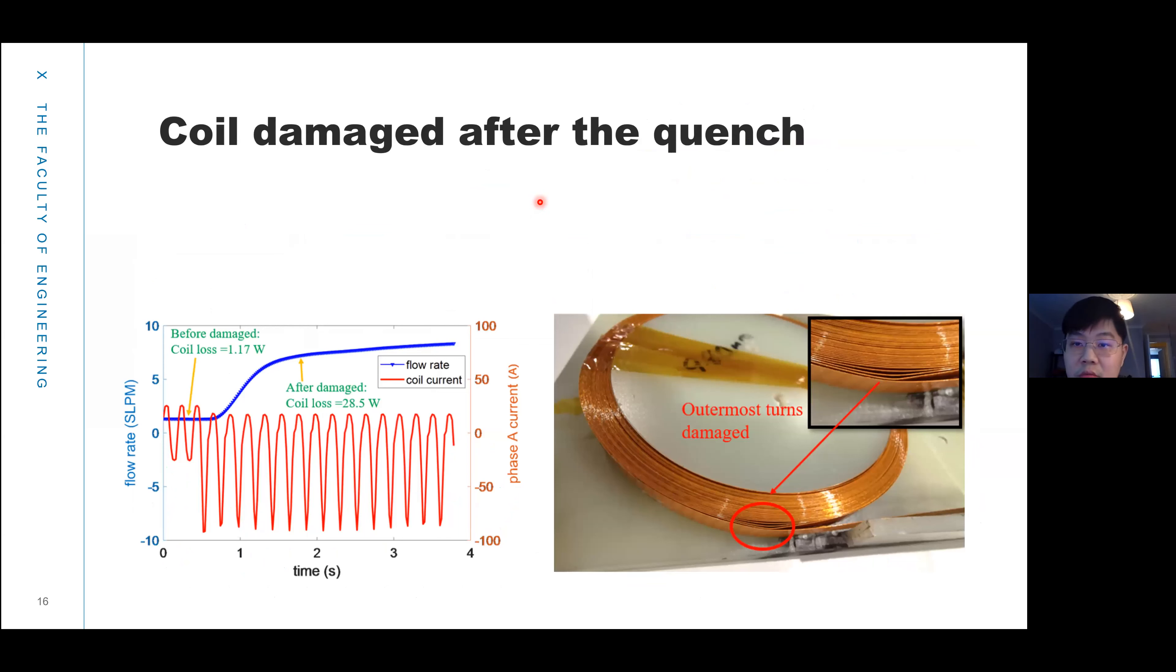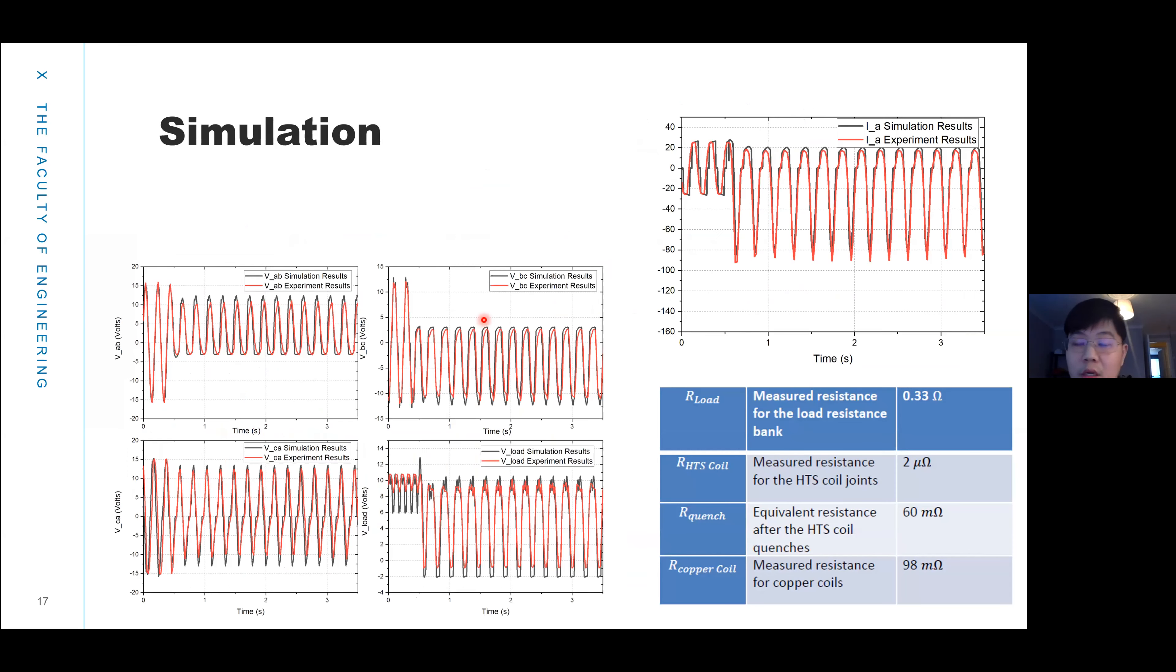After the short circuit, we brought the coil out and found the outermost turn has damage. We also did simulation using the parameters measured. This is the resistance for the HTS coil before the short circuit, and this is the resistance after the short circuit. We measured the copper coil resistance for phase B and phase C and did a simulation. We found the simulation result and the experimental result agreed well.